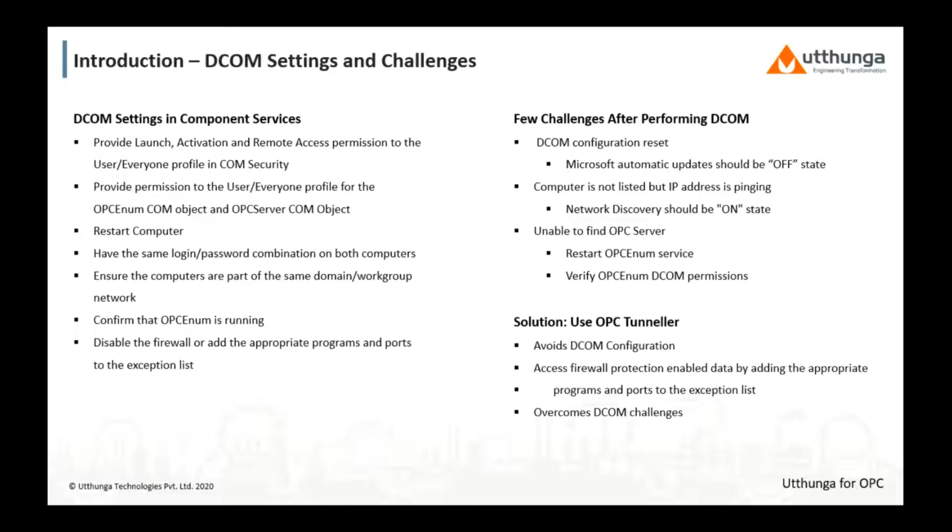So without using OPC Tunneller, generally what does the end user do for the DCOM settings? You need to go to Component Services and provide the permission for launching, activation, and remote access, either for a specific user or for everyone. And also you need to provide permission for the OPC server COM object as well as OPC Enum to discover the server.